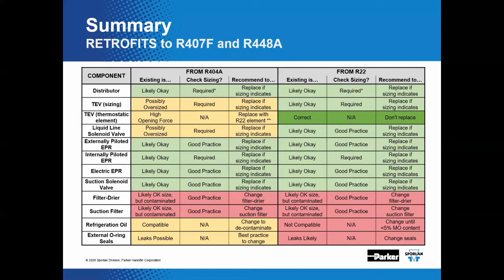As you can see, there's quite a bit of green, probably okay, if you will, on this chart. And there's some yellow, which indicates caution on the liquid side for 404A systems. We do have an intermix of yellow and red down here on the bottom for filters, oil, and external seal. Red means probably not okay, something that needs some extra consideration. And keep in mind, a leak-tight, clean, dry system is truly a benefit to everybody.